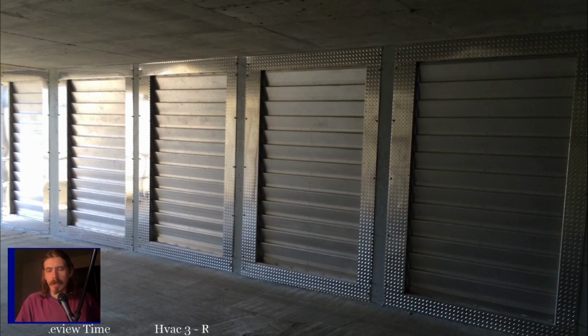So this is a good way. This is a relatively good introduction into that, in section 4.2. But the biggest thing is trying to understand what works for you and what your approach is. Like when we talked about sequences of operation, my method of checking low voltage first so that I can verify stuff before it. If you've got 24 volts, it tells you high voltage is coming in and getting to the low voltage side. We've got low voltage, so I know everything before that is good. So it's a good place to start to make sure I'm not looking for a problem on my power side or something. Generally speaking, as long as you're pretty careful about how you approach it.